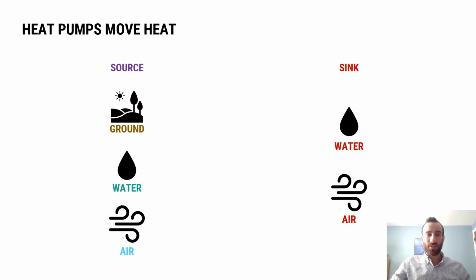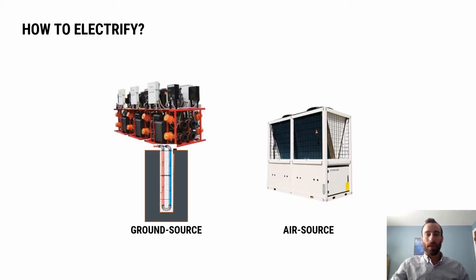So heat pumps, we differentiate in terms of the way they move that heat, where they take the heat from, their source, which is ground, water, or air, and where they move heat to, their sink, which are the two typical fluids we use to heat and cool buildings, water and air. So really common types of heat pumps you're already familiar with are probably ground source heat pumps or geothermal, and air source heat pumps, which include air to water heat pumps shown here, but also heat pumps that are really common like mini splits.